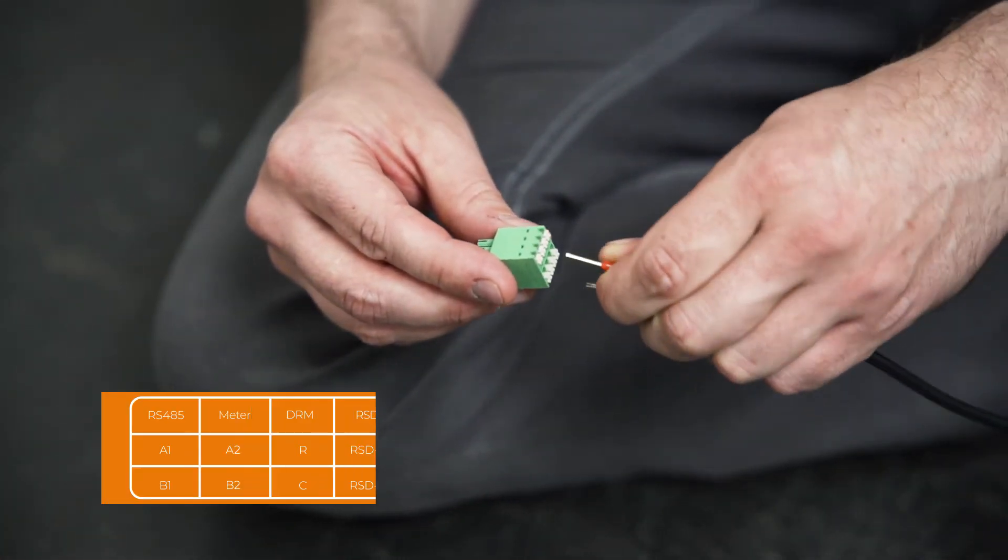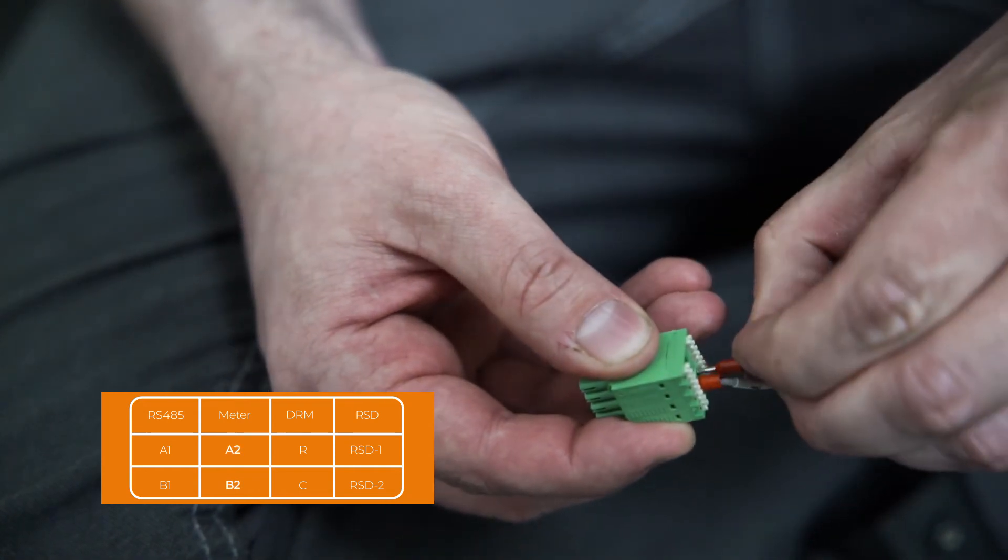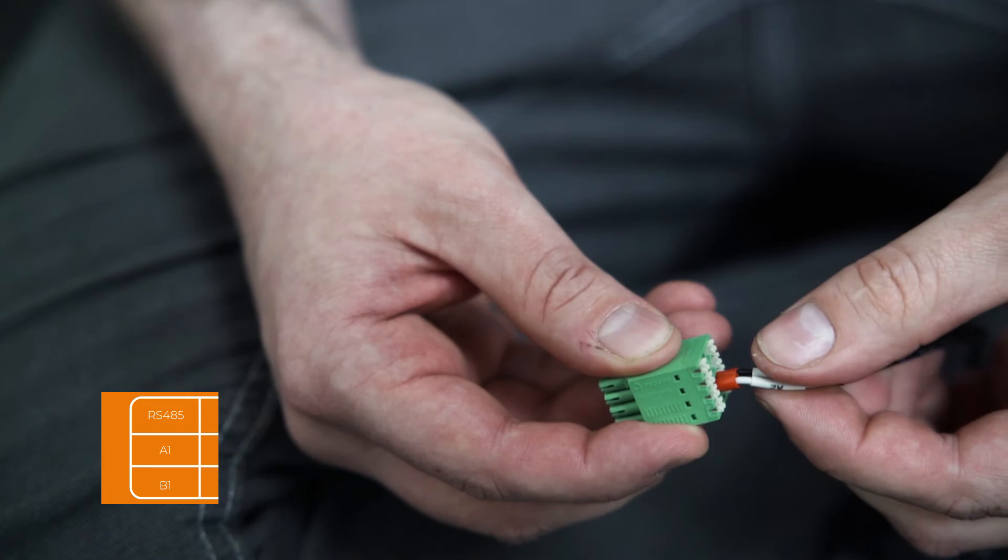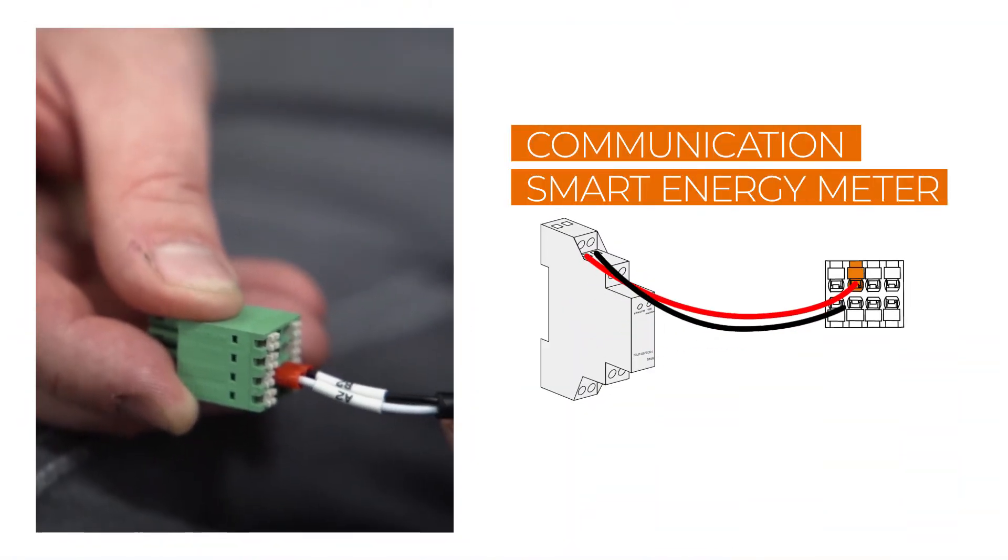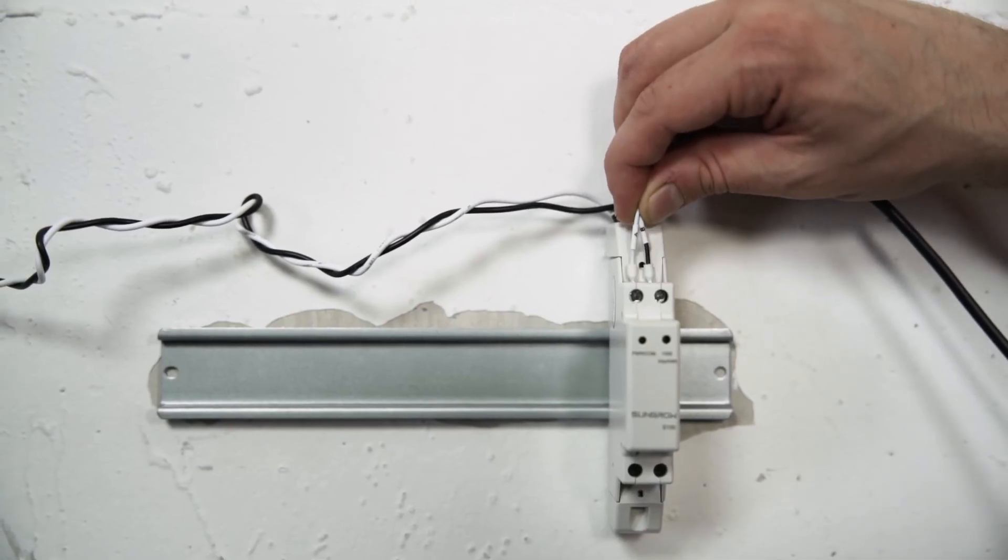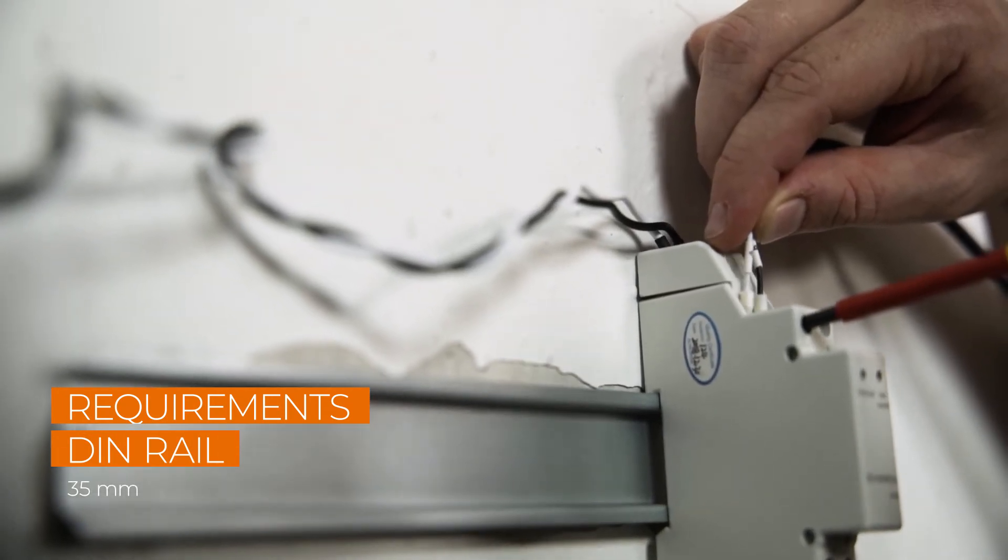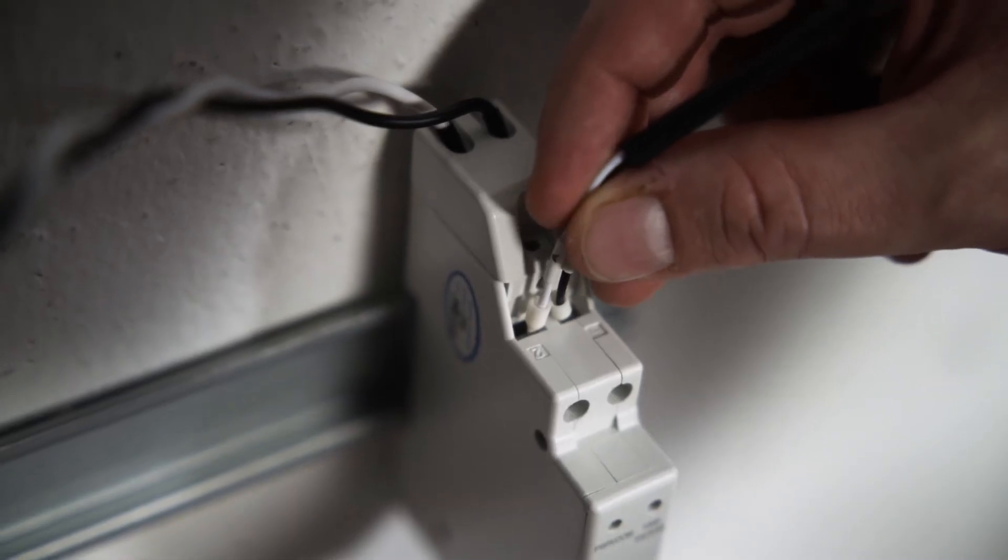At the left side of the inverter, you will find a table with information about which cable has to be plugged into which port. The smart meter is connected to the ports A2 and B2. The other end of the cable needs to be connected to the smart meter itself. Mount the meter to a DIN rail and connect the communication cable RS485A to pin 2 and RS485B to pin 5.